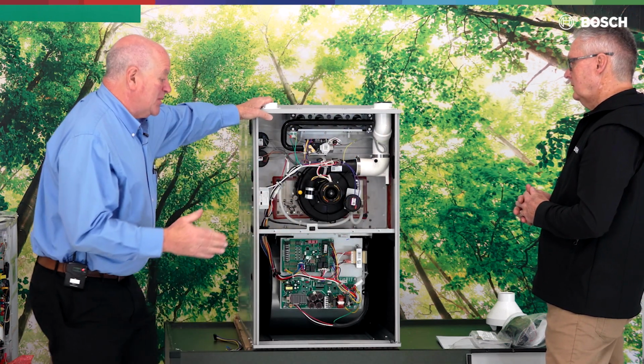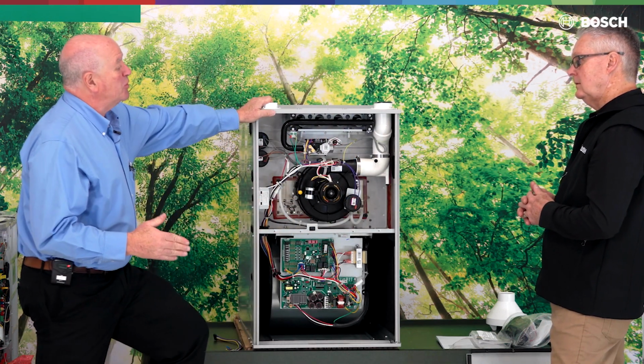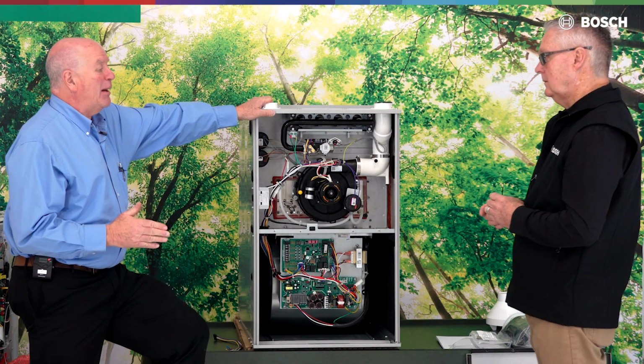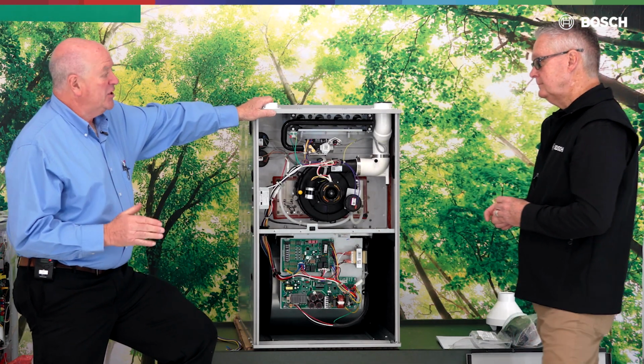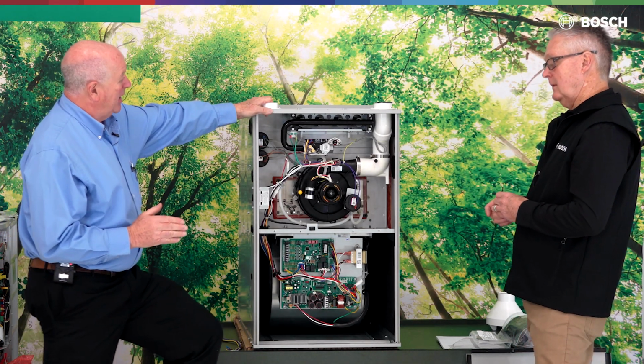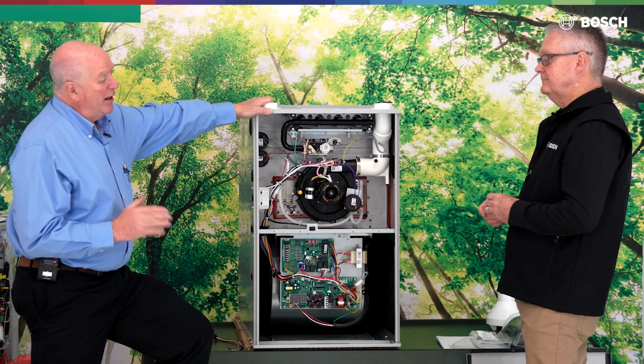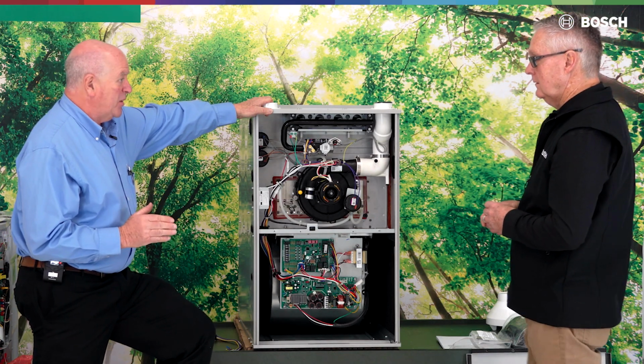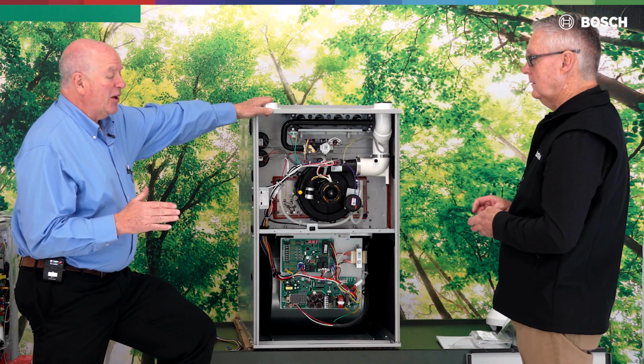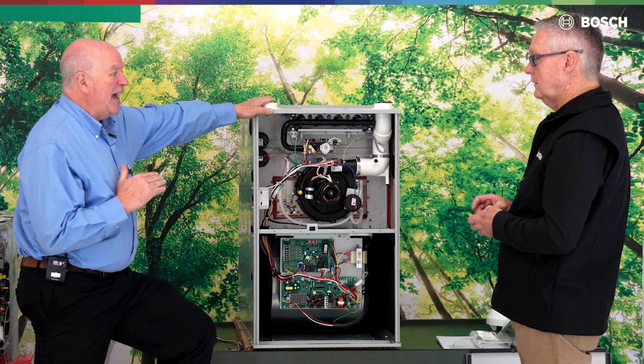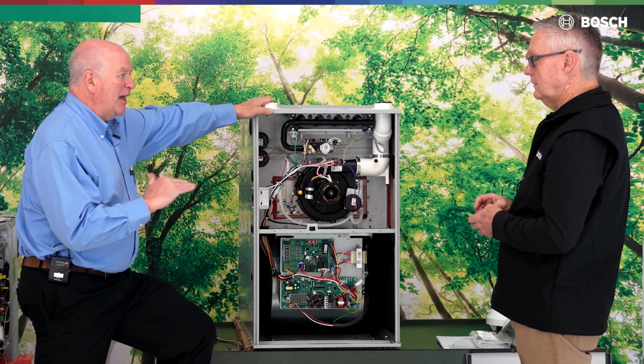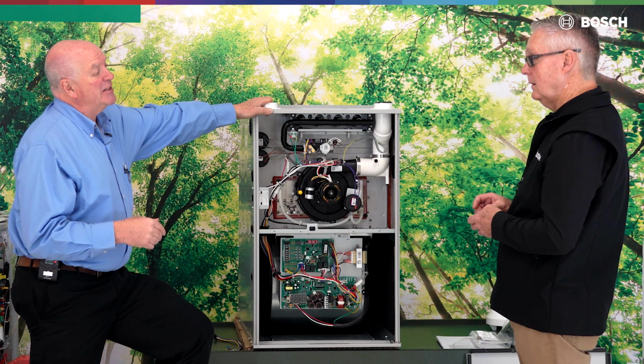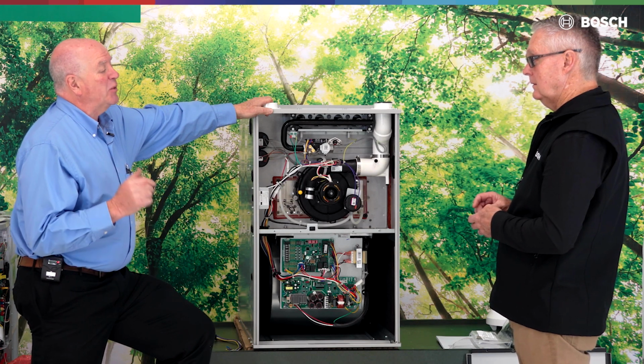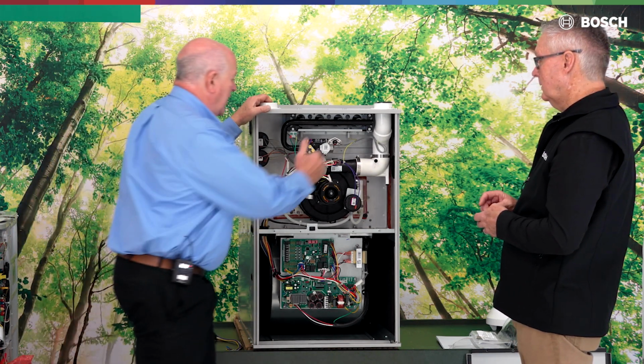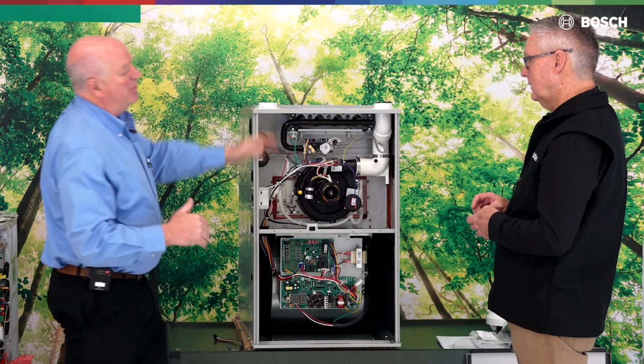Fred, I don't know if you've experienced this, but there have been times with people on LP that have problems with it lighting. One is in real cold weather when your regulator's not big enough to handle that boil off. In one case, one of our other trainers had a real issue with a flame out every Saturday morning at 10 o'clock. He happened to be there at that time and found it was when the generator kicked on, lowering the incoming gas pressure enough to not let it combust properly.